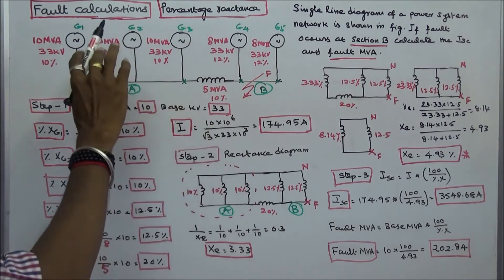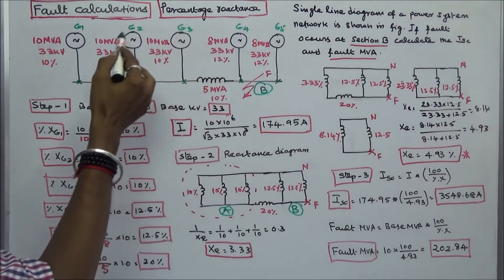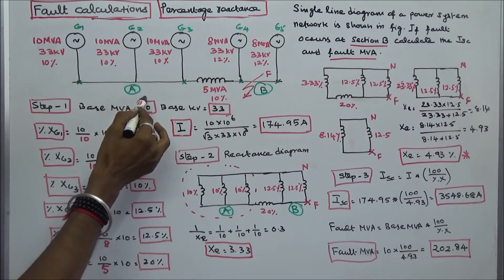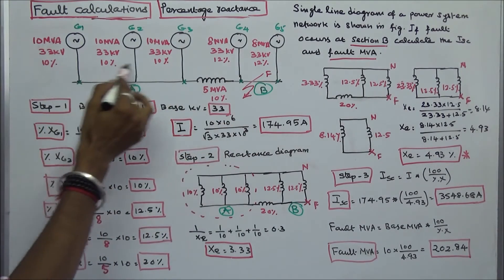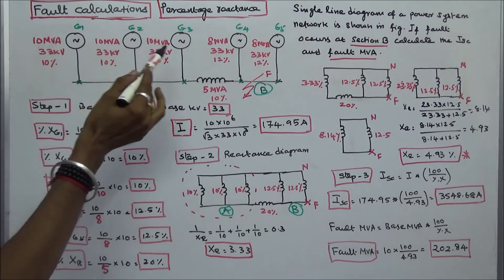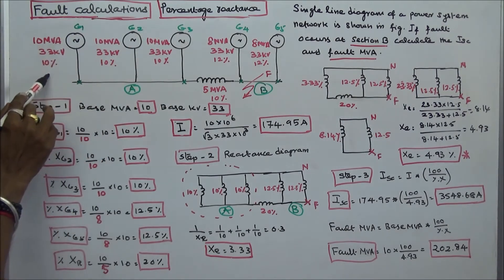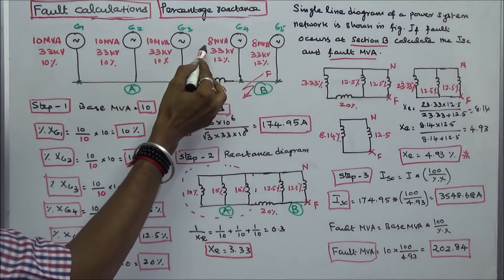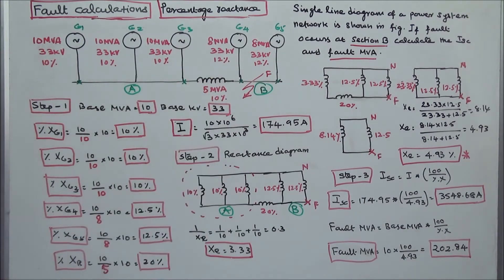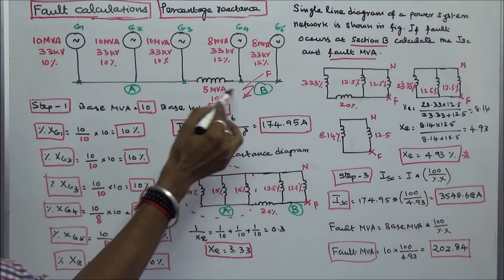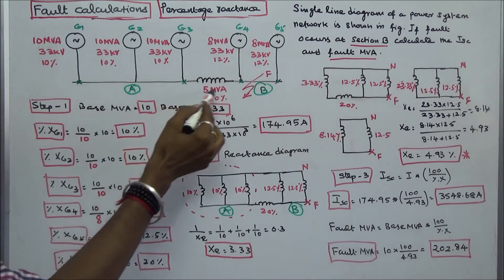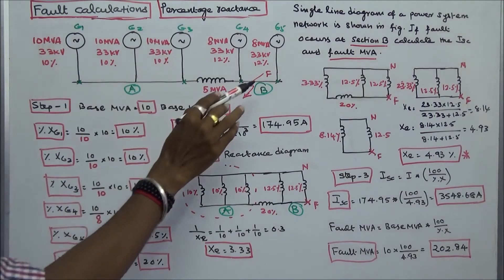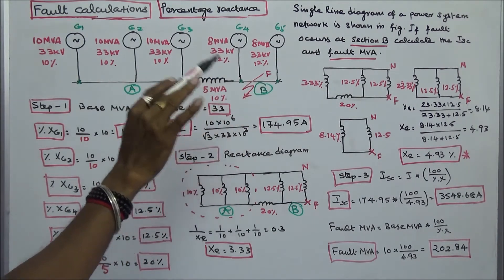This worked problem on symmetrical fault calculation shows a single line diagram of a power system network consisting of two sections, A and B. Section A has three generators, each rated 10 MVA, 33 kV with 10% sub-transient reactance. Section B has two generators, each rated 8 MVA, 33 kV with 12% reactance. Sections A and B are interconnected via a reactor rated 5 MVA with 10% reactance. The question: if a fault occurs at section B, calculate the short circuit current and fault MVA.